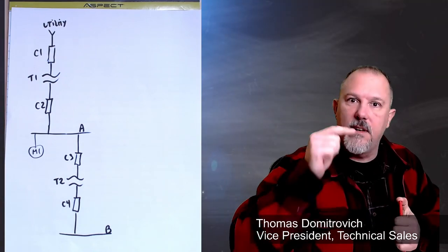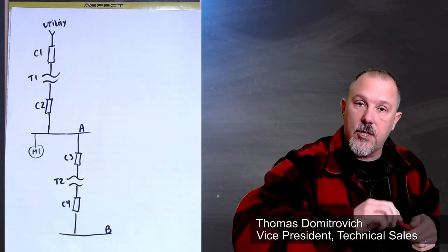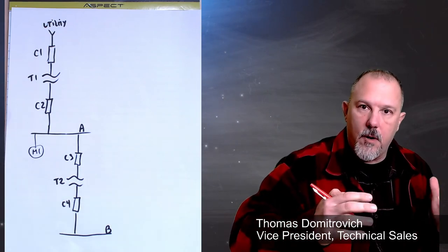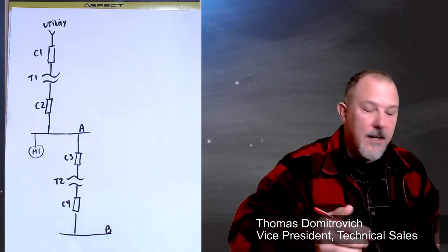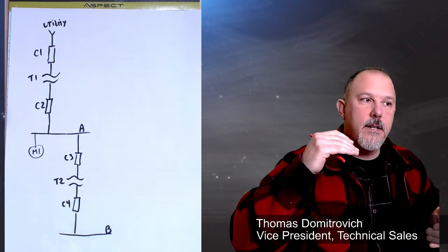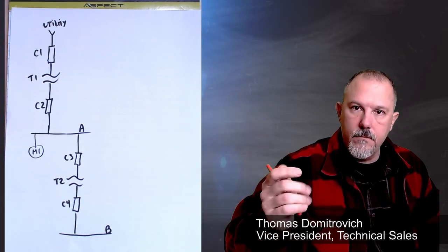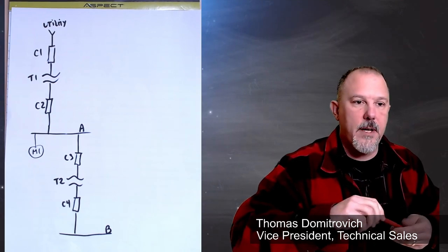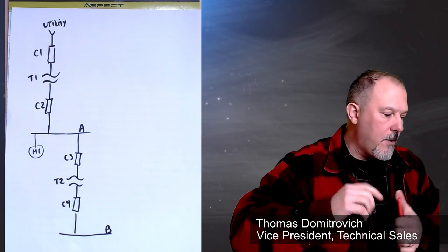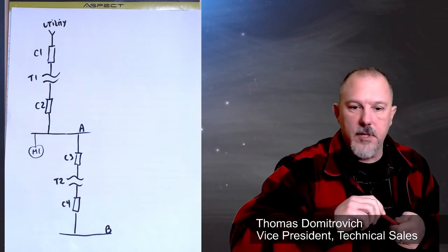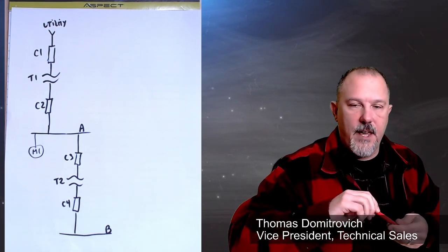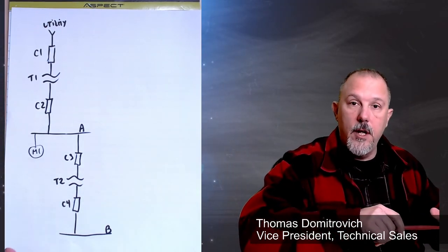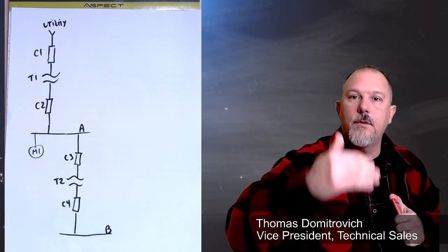But I know since I put it up there on Saturday, you guys have been researching per unit. And you'll know that when I'm doing a per unit evaluation for a power distribution system, I'm going to assume a KVA base value. And if you look in some books, they'll tell you pick an MVA base of some number, or pick one MVA and do everything with regard to one MVA of a base KVA. But my recommendation is that you should pick the KVA of one of your transformers and make that your KVA base for the entire project.